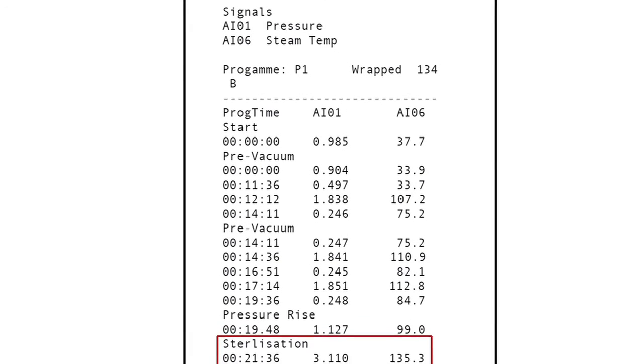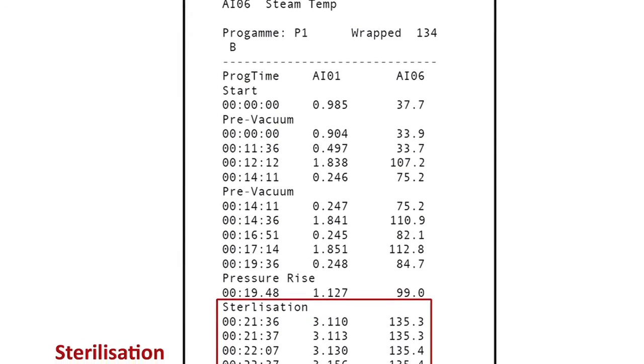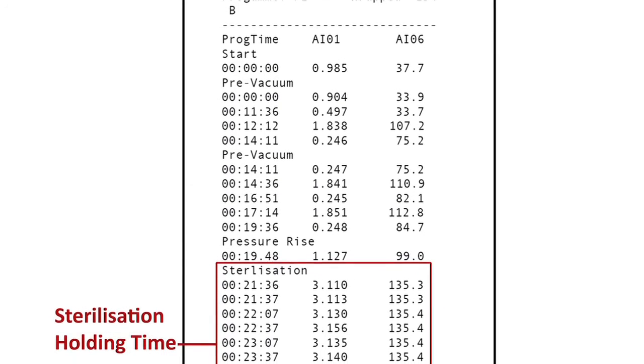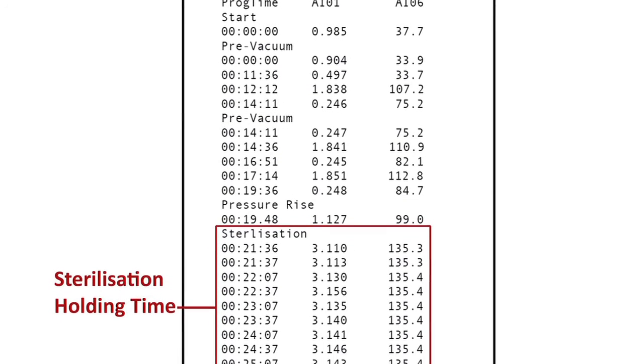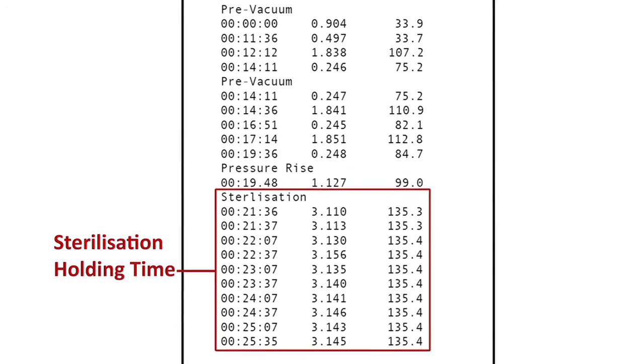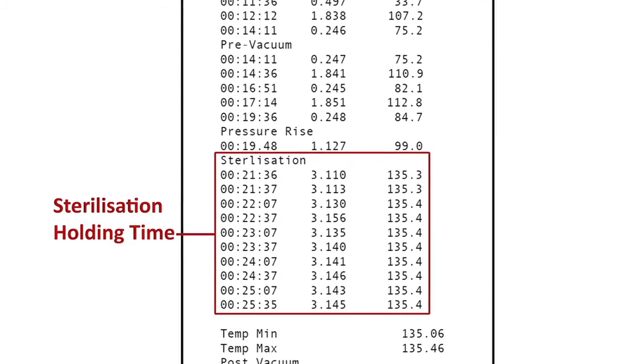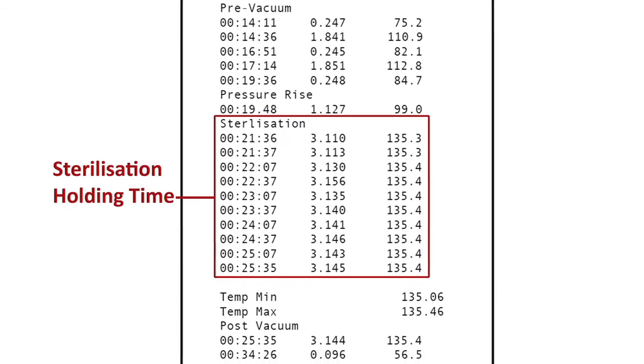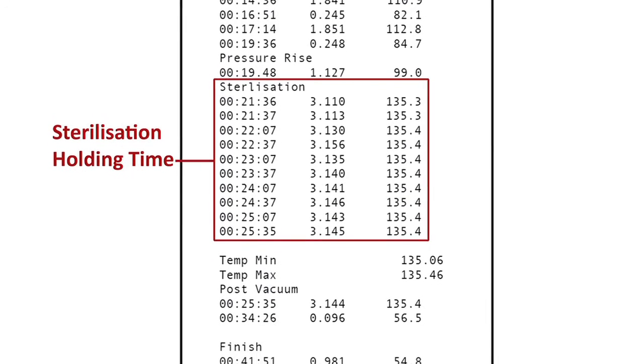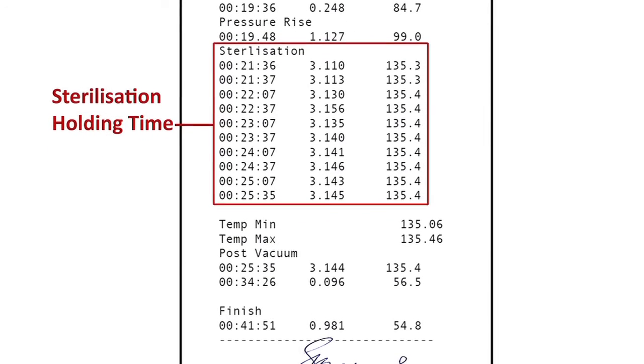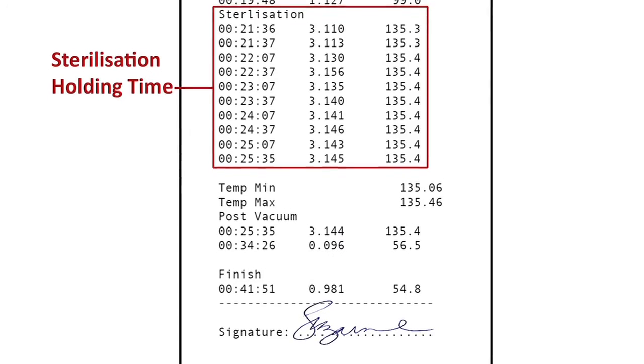The sterilisation holding time is the length of time the autoclave has reached and maintained 134 degrees centigrade and is the most important detail on the graph. 3 to 4 minutes at 134 degrees centigrade is required for effective sterilisation. Remember to sign the graph printout after each cycle is complete.